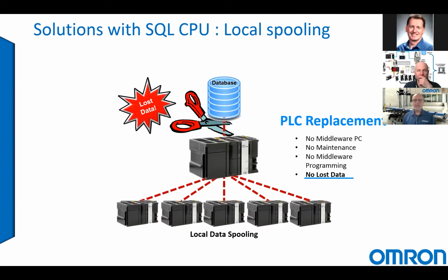If we have a disconnection, we have local spooling functions, up to one megabyte of information that you can spool before reconnecting to the database. As a secondary option, we can also do flat files within the controller, residing on an SD card that's part of the controller. Whenever the connection is back, you can read that flat file from the SD card and send it up to the database.